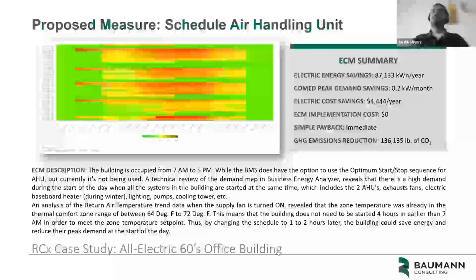So by implementing this measure, the building will be able to save almost 87,000 kilowatt hours of energy annually. The implementation cost for this particular building was zero, just because this is something that can be done internally by the building engineer. It was just about changing the schedule. Instead of starting the system at 2 a.m., he was just supposed to start the system at 6 a.m. And so that's why the implementation cost for this ECM was zero.